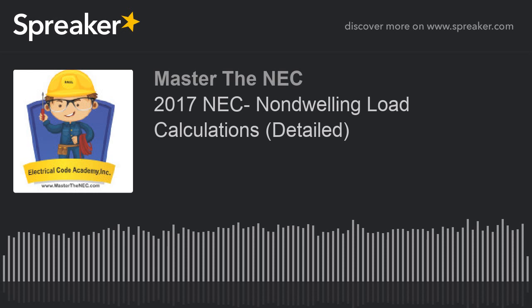And I got a 230 amp rated conductor. And can I use a 230 amp rated conductor on a 225 amp rated breaker? Absolutely. It's fine there. So I'm good. So here, my size would be a 4-aught, which is good for 230 amperes. Okay? So that's my scenario when I'm dealing with that, and that's how I'm going to size the conductor.